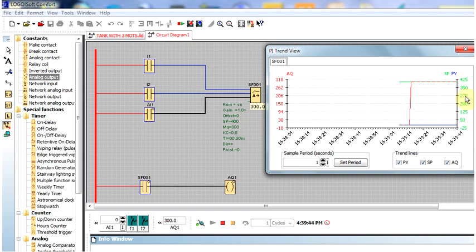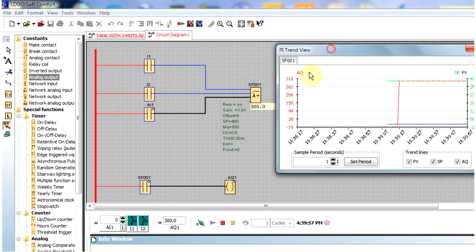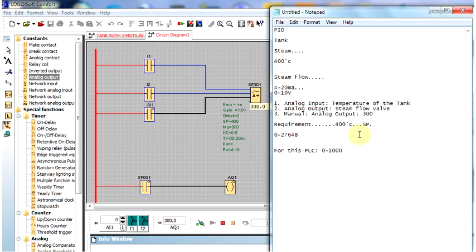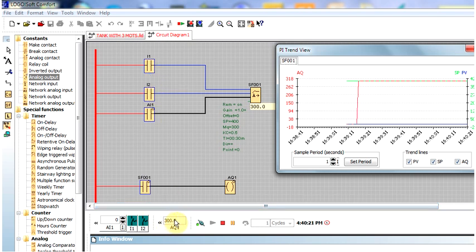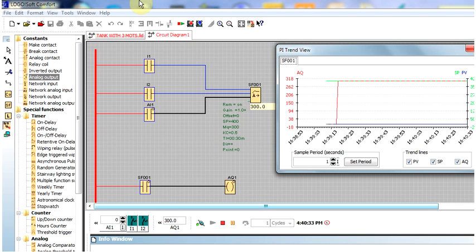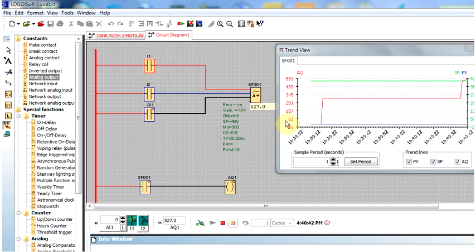I said we applied a manual control and kept the manual output at 300. The function is currently running in manual because I1 is 0. You can see that the output is constant at 300 while the temperature is at 0 — this is manual mode running. Now for the automatic system, I will turn on I1. When I turn on I1, you can see the output AQ in the graph is now changing — it is trying to reach 400 degrees centigrade.